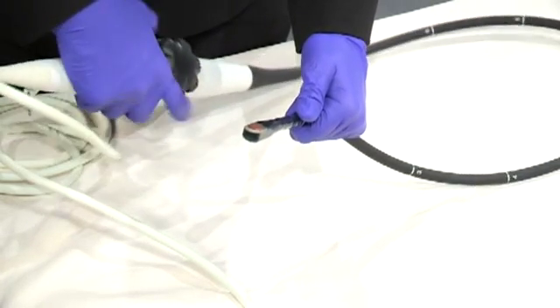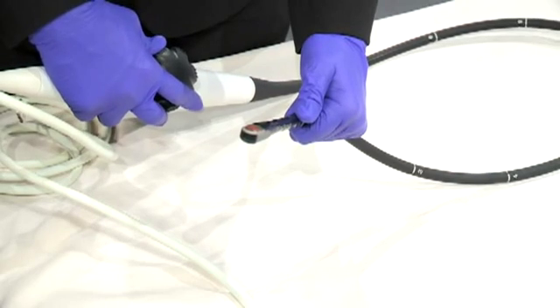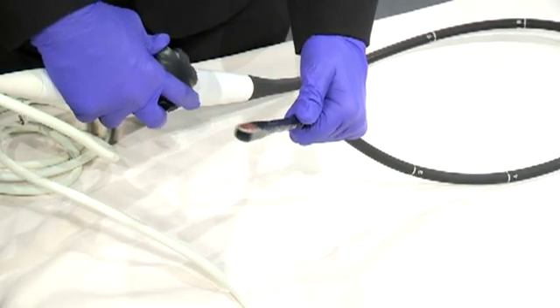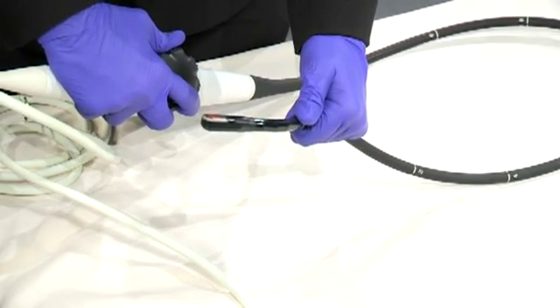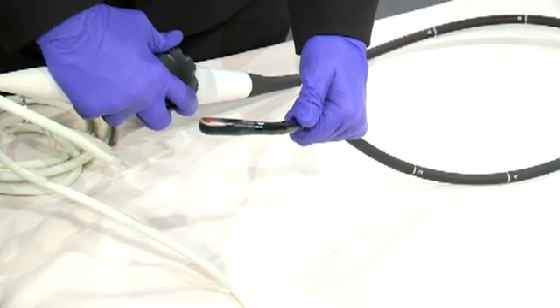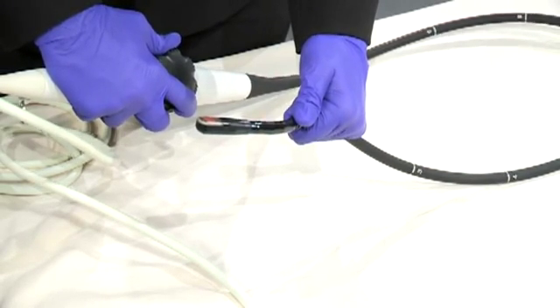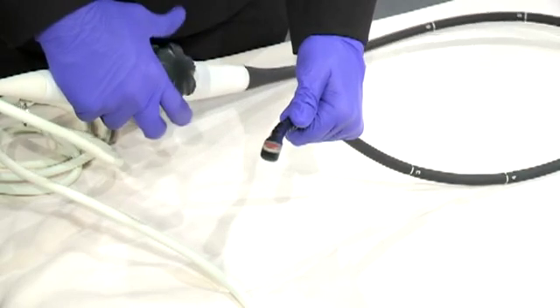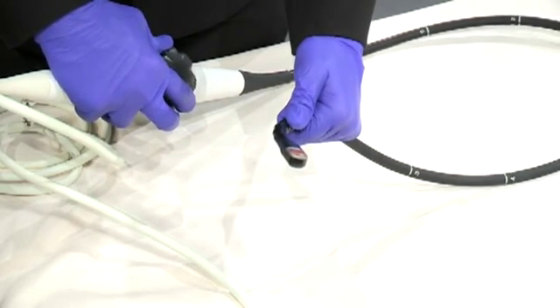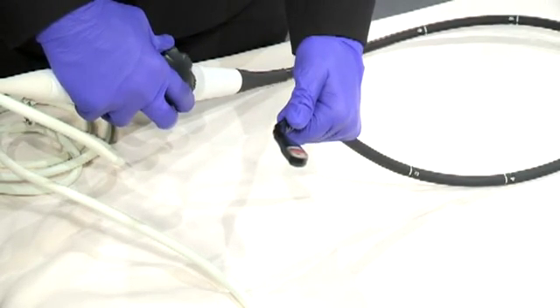Operating the upper wheel controls. Turning the upper wheel clockwise to deflect the endoscope tip right to approximately 40 degrees. Counterclockwise rotation of the upper wheel will deflect the tip to the left 40 degrees.